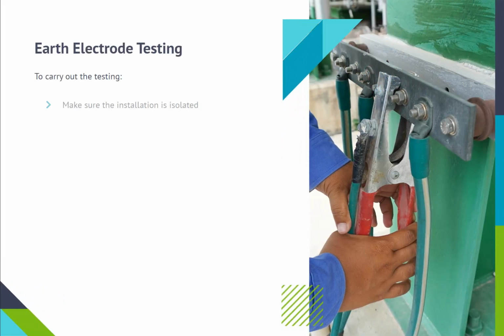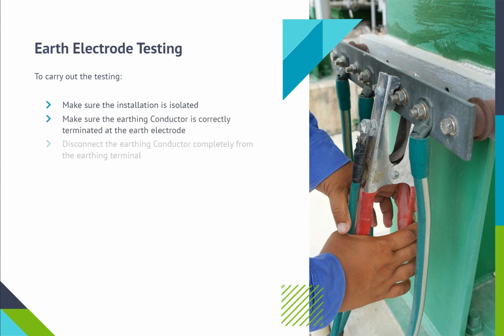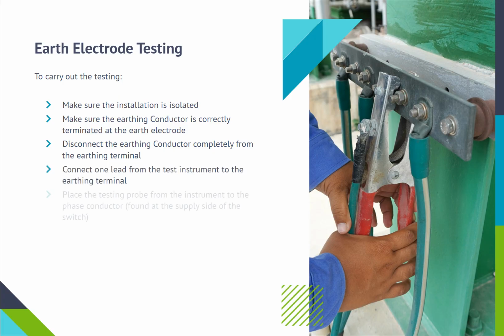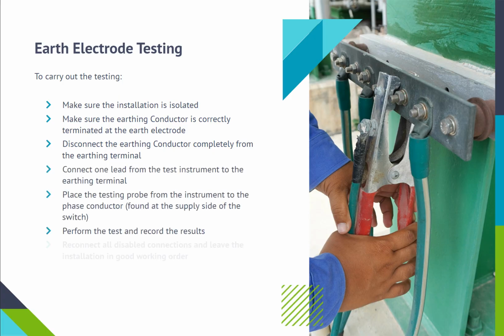To carry out the testing, make sure the installation is isolated. Make sure the earthing conductor is correctly terminated at the earth electrode. Disconnect the earthing conductor completely from the earthing terminal. Connect one lead from the test instrument to the earthing terminal. Place the testing probe from the instrument to the phase conductor found at the supply side of the switch. Perform the test and record the results. Reconnect all disabled connections and leave the installation in good working order.